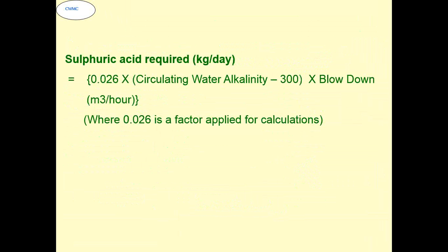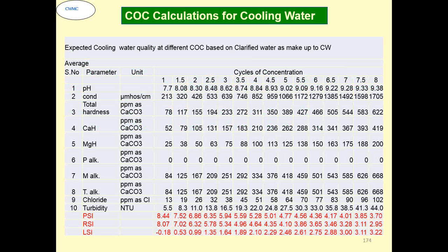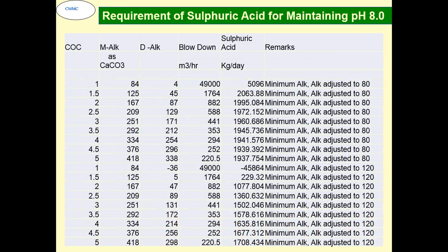Normally the pH is controlled at a certain level. To control the pH, we use sulfuric acid. This is the formula that we can use for calculating the sulfuric acid required per day in terms of kg per day. Simply it is 0.026 multiplied by the circulating water alkalinity minus the alkalinity that we want to maintain. I have put 300 here, but whatever alkalinity we want to maintain, I have to put there. So whatever the delta alkalinity that comes, multiplied by blowdown in cubic meters per hour, will give you sulfuric acid in kg per day that is required. This is a typical calculation for cycles of concentration and the acid that is required at different COC.